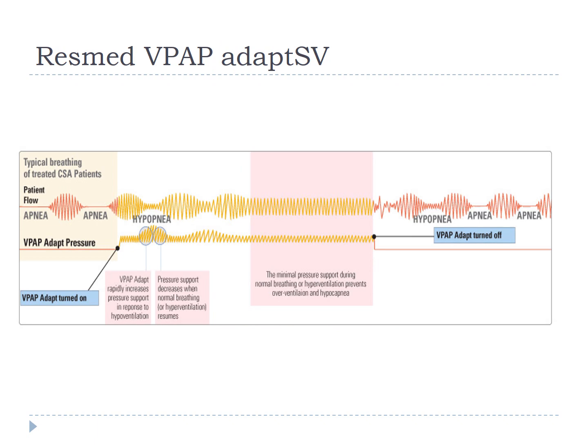Now here's an example of ResMed's VPAP Adapt SV. If you look starting at the left-hand side of your screen, you see the typical breathing for a central sleep apnea patient. So there's an apneic event, and then they take some nice deep breaths, and then it starts to wane again. They have another apneic event, and then they start to breathe. And then when it goes to the yellow, you see they turn the VPAP Adapt on. And you see when the patient starts to decrease in their breathing, look how quickly the VPAP Adapt adjusts to it and starts delivering a higher pressure.